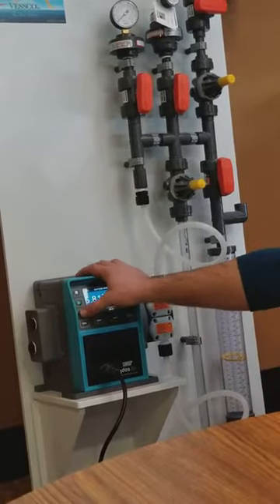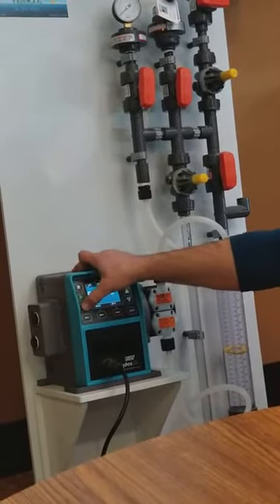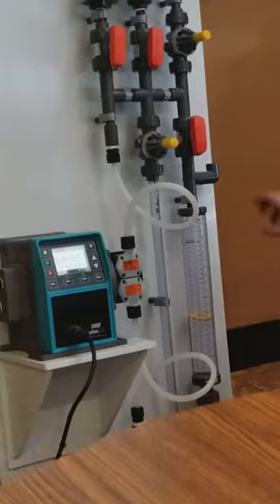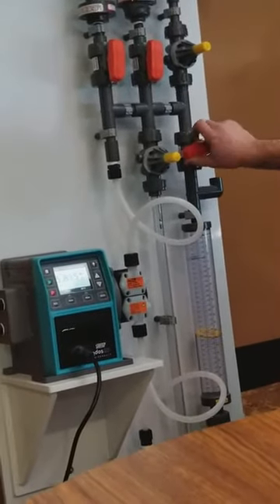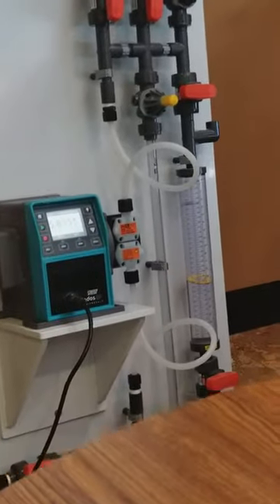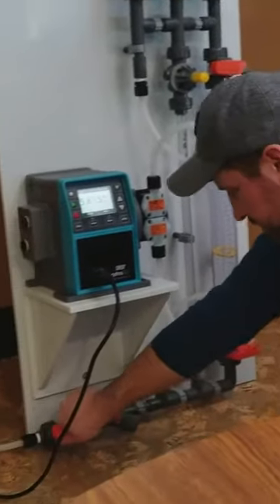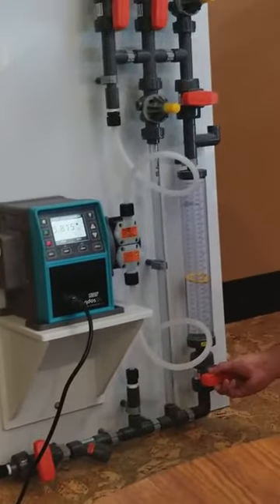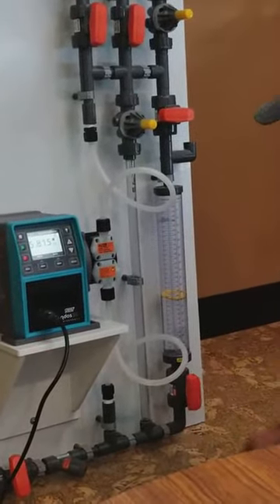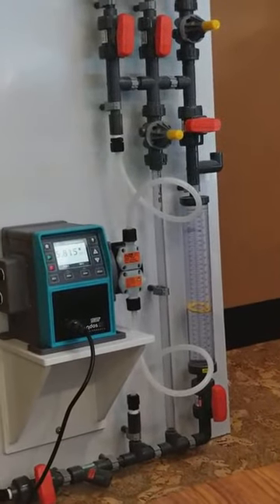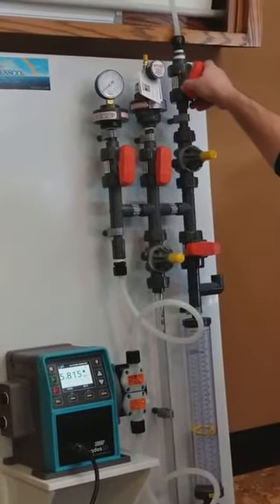So that should be enough volume that we should need for this. So we'll go ahead and stop the pump. At that time, we go ahead and close our fill for our calibration column. We're going to close our inlet valve, open the feed of our calibration column. We're going to go ahead and make sure we open our discharge.